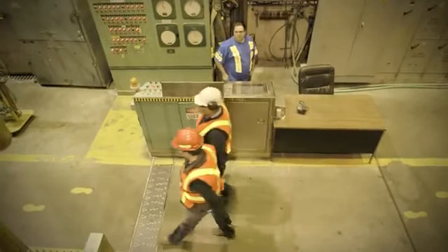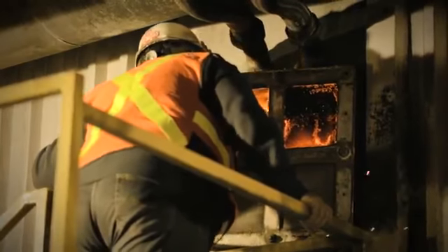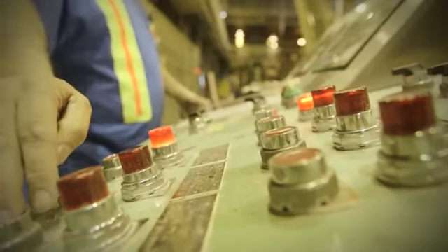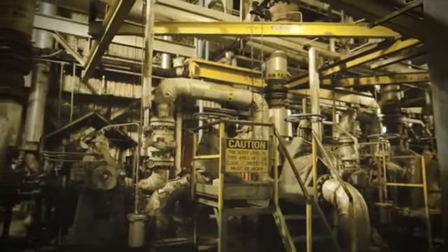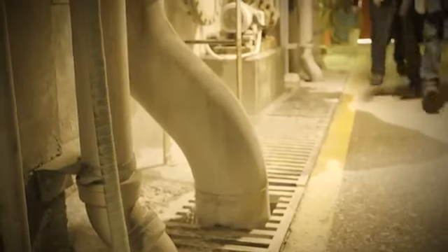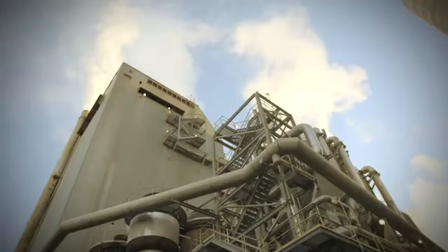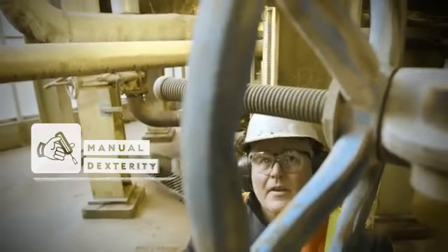Wow. Typical day, if you're a field guy, it consists of doing rounds on the boiler. We're required to do every 2 hours. You have to go and check your peripheral equipment out in the field and make sure it's running. There is instrumentation that measures the process of the boiler, and we need to make sure the access to those is kept clean. And then there's all of the auxiliary equipment that's out there, pumps and valves and those kinds of things that from time to time fail. And so we need to go and isolate and put on standby equipment if we have standby equipment. Hopefully we do. Most boilers do. And so there's a lot of manual type labor for the field position.